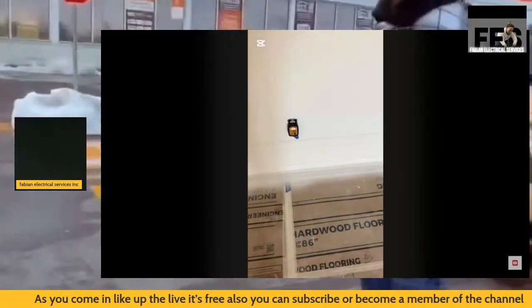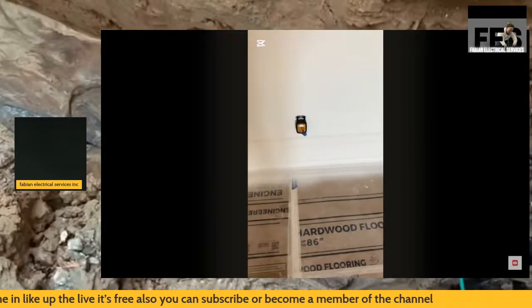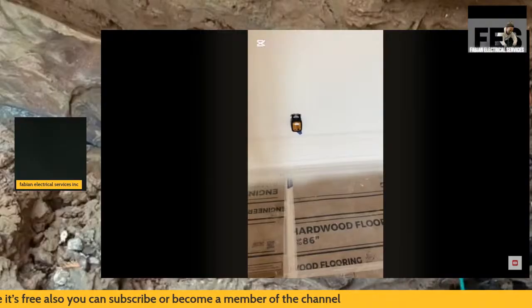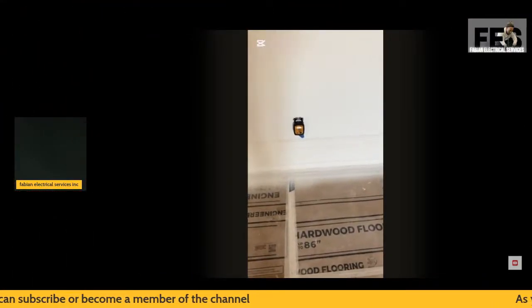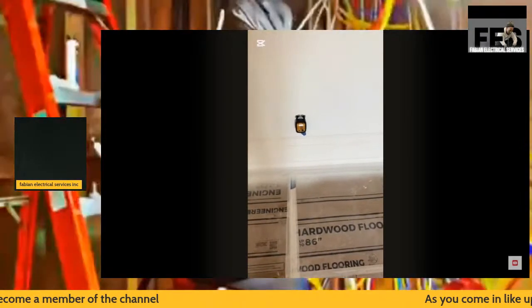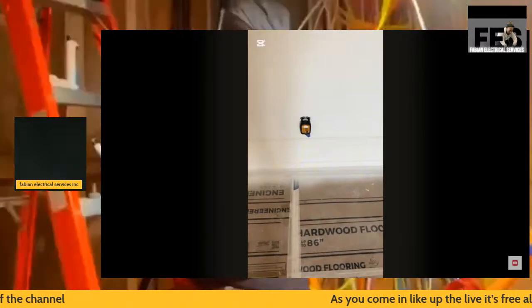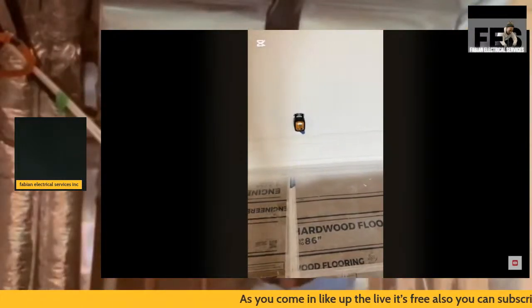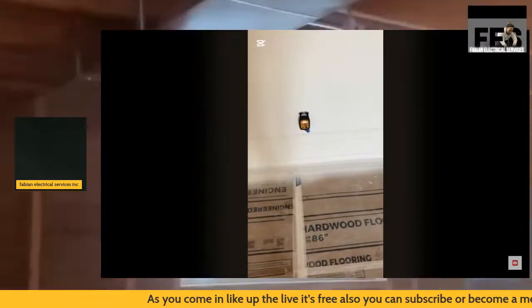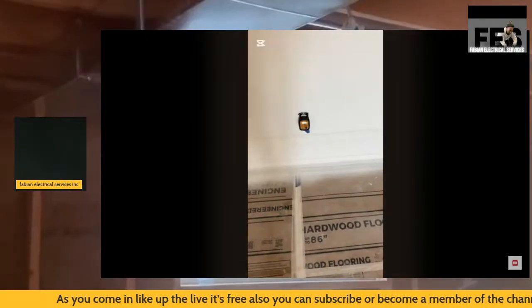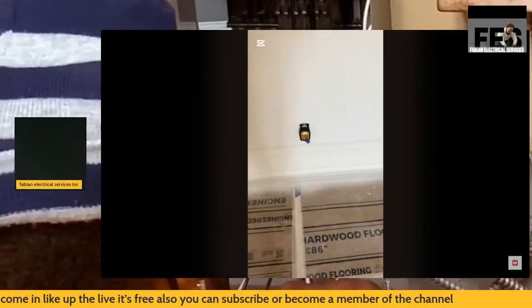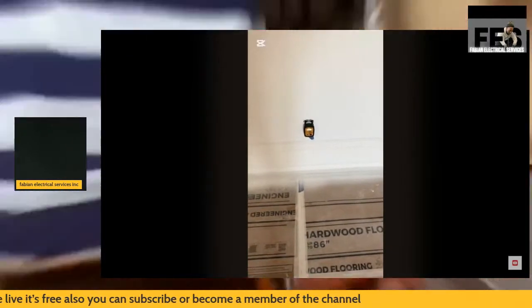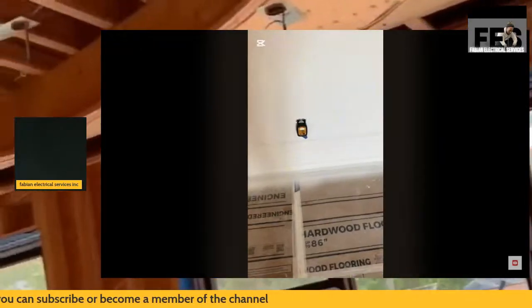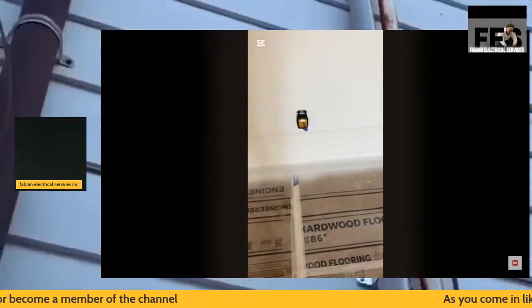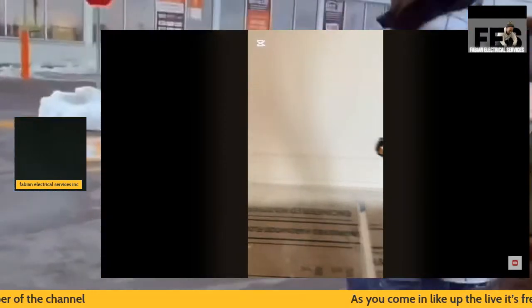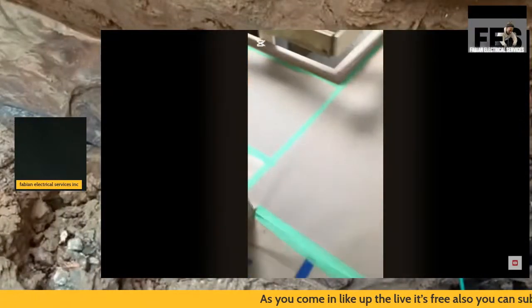I'm going to put this theory to the test. I've had this plug-in tester, great for troubleshooting to let you know if your electrical circuit is running power. I have it plugged in right now. I'm going to go to the panel and start turning my breakers on. Once it's the correct breaker, this should turn on green and beep to notify me. Let's put this to the test.